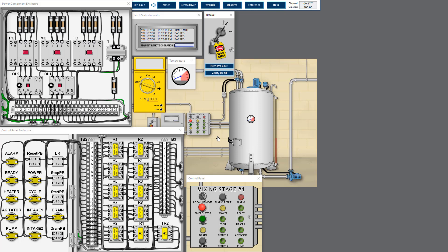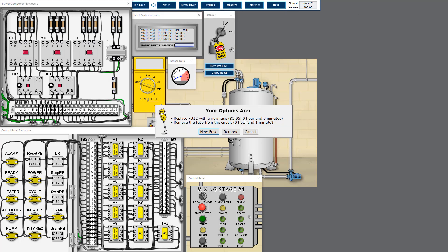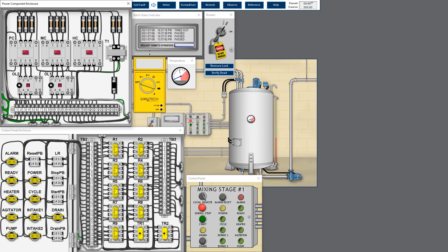To check for an earth fault or device internally short circuit, we have to open both ends of the connection. I prefer to open the common live and the common neutral. In this case, I remove the fuse and disconnect the common neutral. Now we have both ends open — one at the common live and the other at the common neutral.